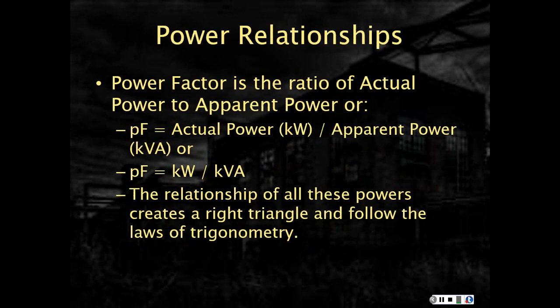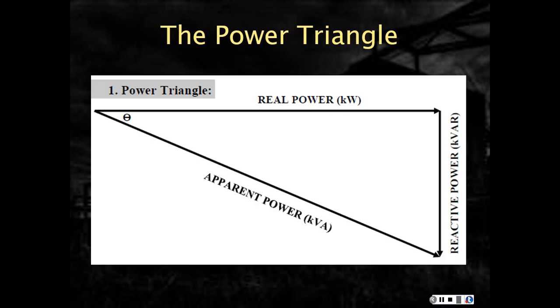Now, how are these 3 powers related to each other? First of all, power factor is the ratio of actual power, or working power, to apparent power, or kW divided by kVA. If we take a look at the relationship of all 3 of these powers, they actually form a right triangle and follow the laws of trigonometry and the Pythagorean theorem. What you see here on this slide is the relationship of the 3 powers that we just discussed. Real power on the top, kW, which can be measured directly. The reactive power, kVAR, forming a right triangle, also can be measured directly. And then the hypotenuse on the bottom, kVA, apparent power, which has to be calculated.